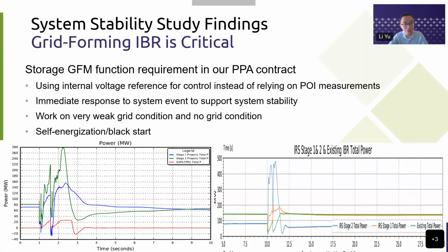After all this study, we revised our GFM function requirement in our standard PPA contract. Basically, we put the GFM function requirement in a more detailed way. We want this storage GFM function to rely on the internal voltage reference instead of the measurement at the POI, to respond immediately to system events and provide system stability, and to work on a very weak grid and even in no-grid conditions, because we believe our grid is going to get weaker and weaker as we have to replace certain fossil generation. Self-energization and black start are also important functions in our storage grid forming requirement. Next slide, please.